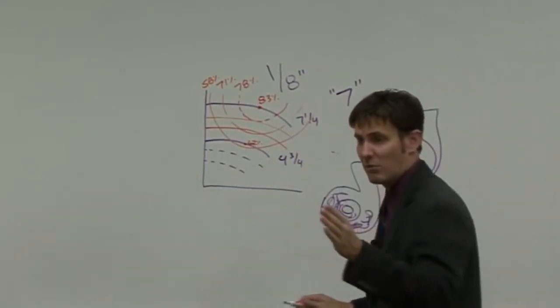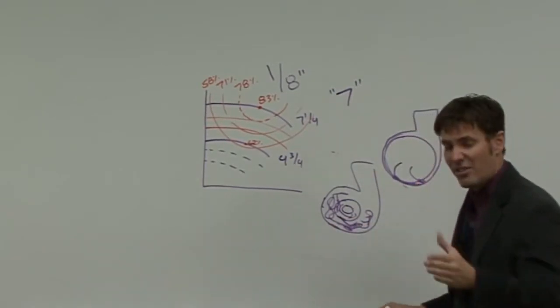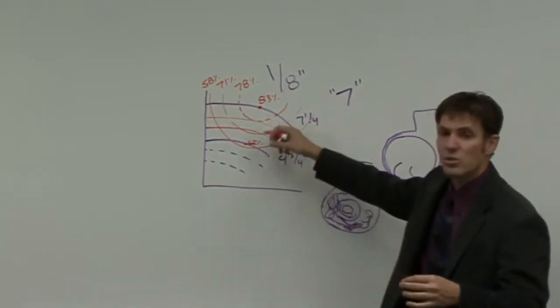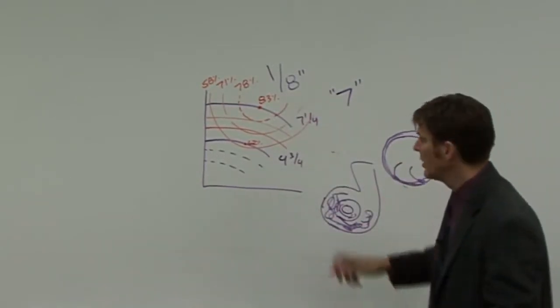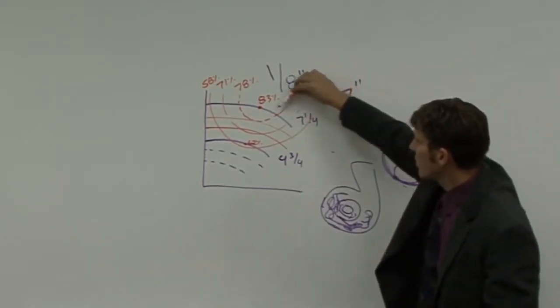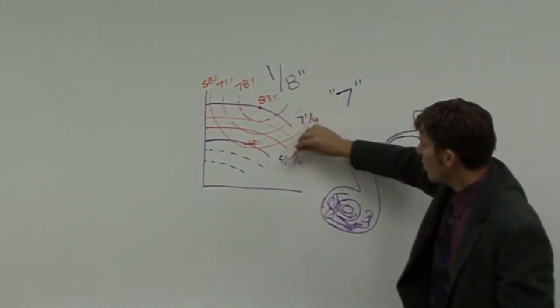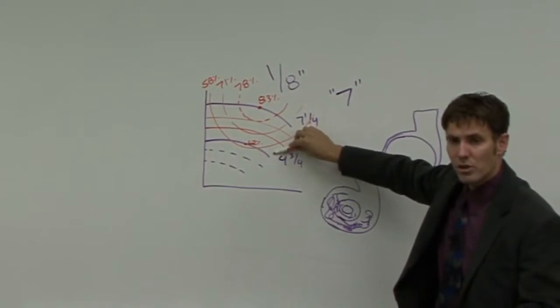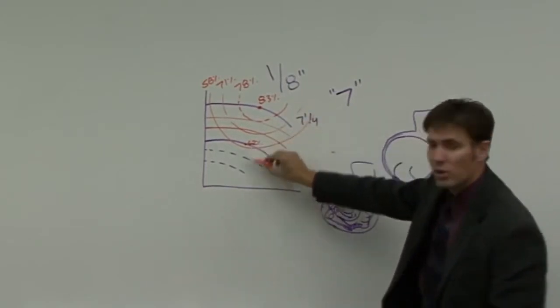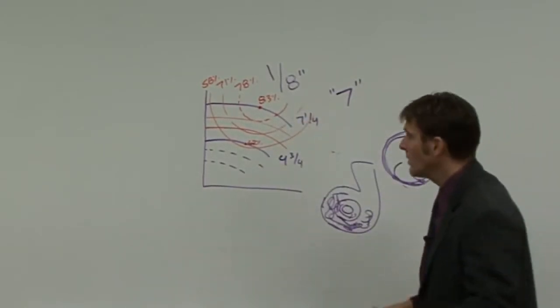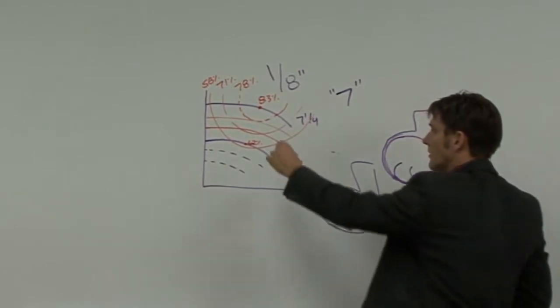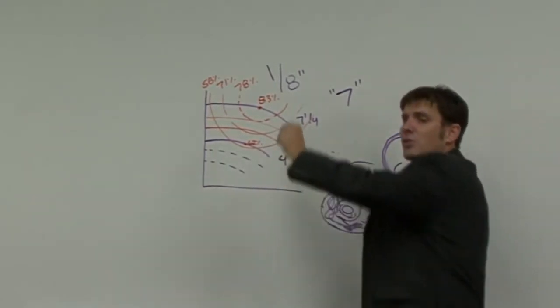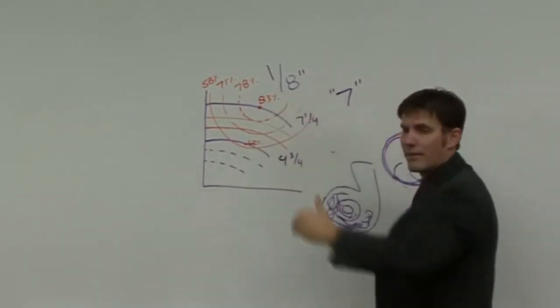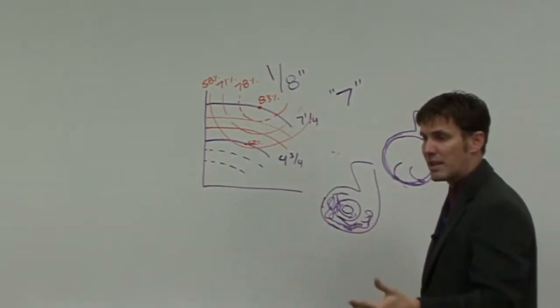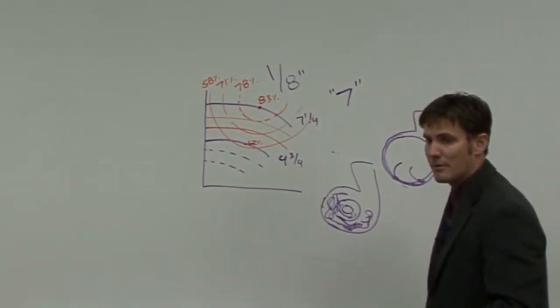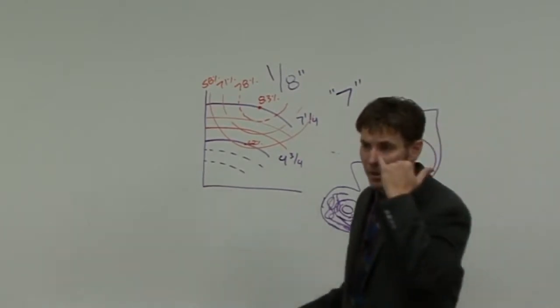Yeah, try that one on. The other nice thing about that is I can untrim the impeller by speeding it back up. I can operate on my 7 1/4 inch curve. I can operate all the way down here to my 4 3/4 inch curve and anywhere between, or even lower, by slowing my pump down. However, I can untrim that too and go back up to my full size curve, my full speed, by speeding that back up. You can't do that when you trim an impeller.